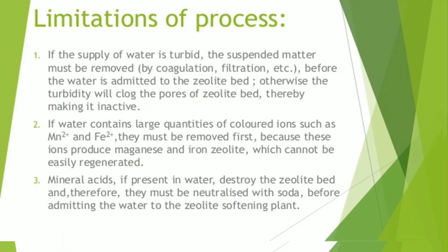Let us study the limitations of the zeolite process. There are many limitations; let us study them one by one. The first limitation is that if the supplied water is turbid or has suspended matter present, the suspended matter must be removed before the water is supplied to the zeolite bed. Otherwise the pores of the zeolite bed will be blocked by the turbidity, thereby making it inactive.